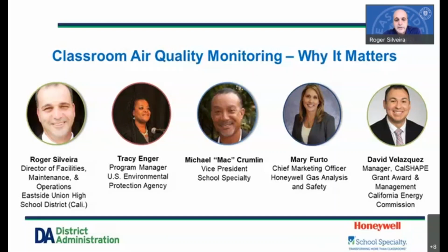Shortly after, I found another cluster of classrooms with similar issues where the ventilation system had failed and there was no fresh air in those classrooms. Right after that, I ran into an article from Lawrence Labs on CO2 levels in classrooms and how that impacts student attendance.